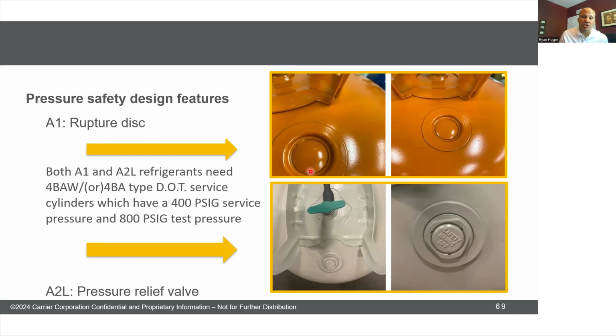The last thing that is changing is that we're getting rid of the rupture discs. So refrigerants you guys have been used to have had these rupture discs for years. Basically, this piece right here is a thinner gauge of metal than the rest of the tank. So when the pressure builds up too high in the tank, it ruptures there instead of blowing up the whole tank like a bomb. It's kind of like a fuse, right? It's designed to break. This is the spot. If it's going to break, this is the spot we want that to happen. We want the fuse to blow instead of the whole electrical circuit to go, right? We want this rupture disc to blow instead of the whole tank.